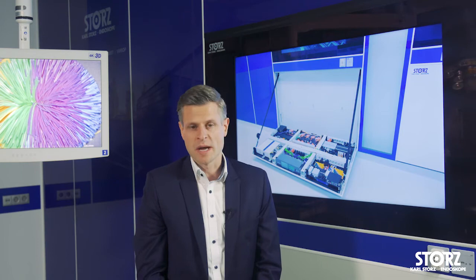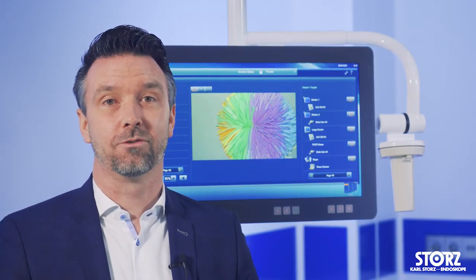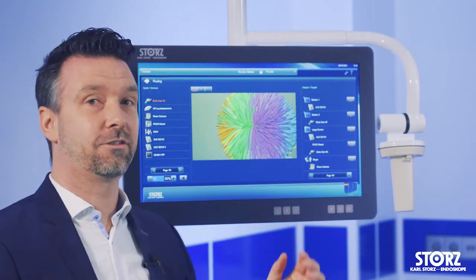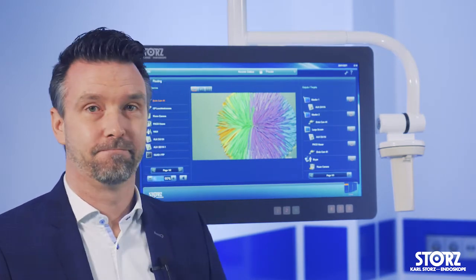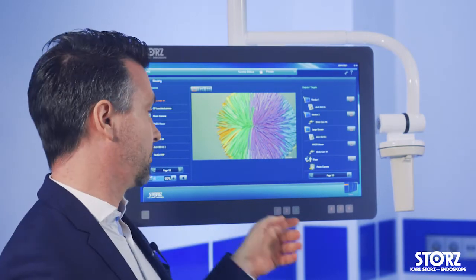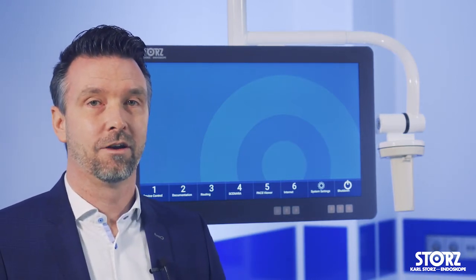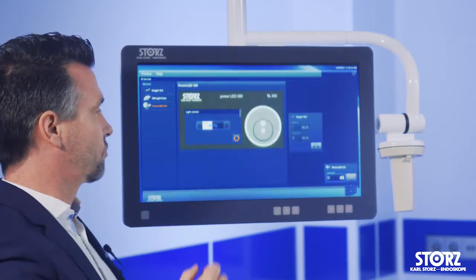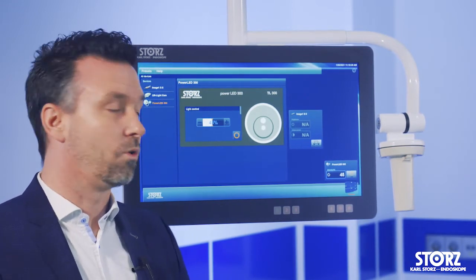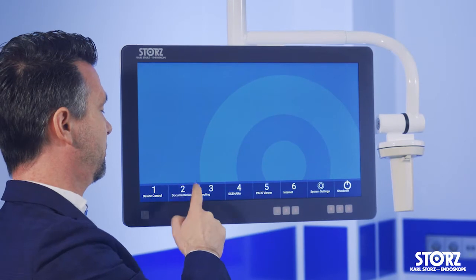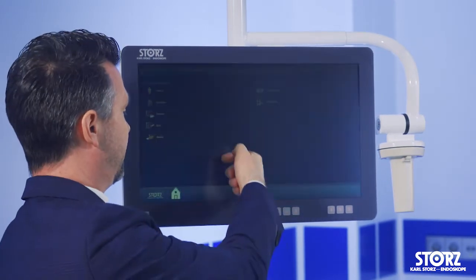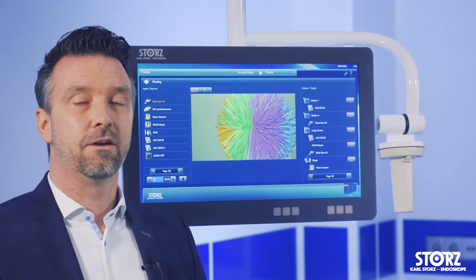Now, please give us a detailed look into the functionalities. The OR 1 system can be controlled from the nurse workstation touchscreen or surgical touchscreen. In the sterile area, a sterile foil is needed. We can use our latest functionality, the swipe control, to open the application home screen. The menu can be customized based on the wanted functionalities — for example, a direct access to our STORZ communication bus, the device control, or our documentation with the AIDA documentation system, as well as our routing module, the audio-video management.